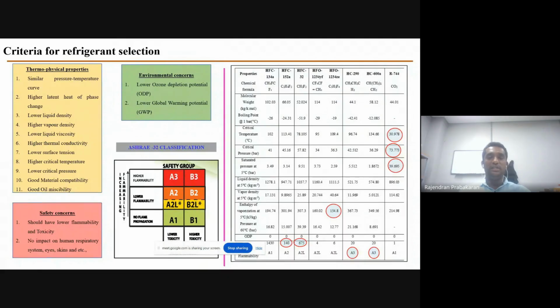Based on the ASHRAE 34 classification, you can see from this figure, there are 6 classifications. Now recently they added 2 more, so 8 classifications based on toxicity and flammability. So it is always expected to have lower toxicity and no flammability. But you can see from the table on the right side, there are different refrigerants, starting from the HFCs like R134a and R152a, from the HFO side R1234yf and ZE, and the last one is hydrocarbon refrigerant.